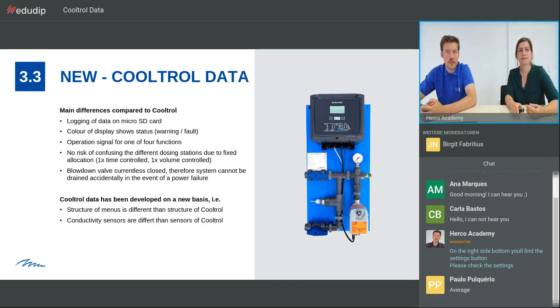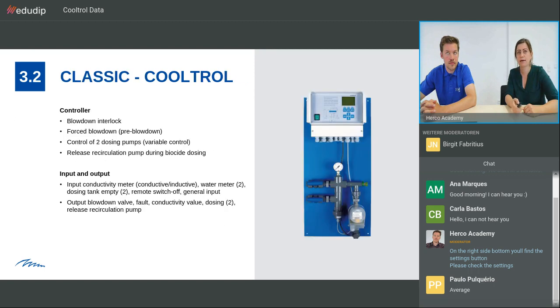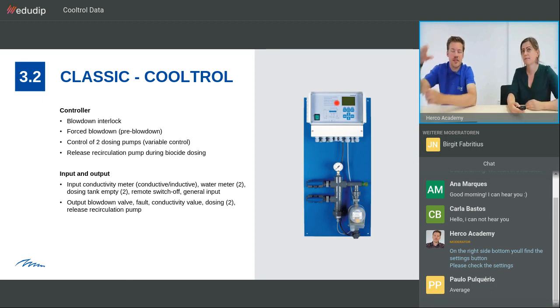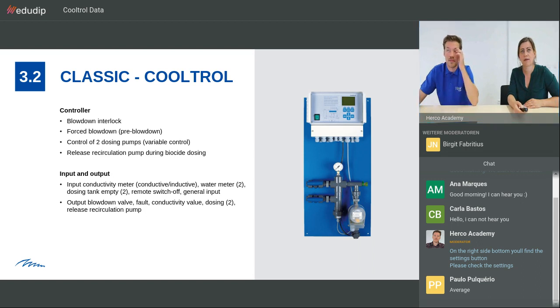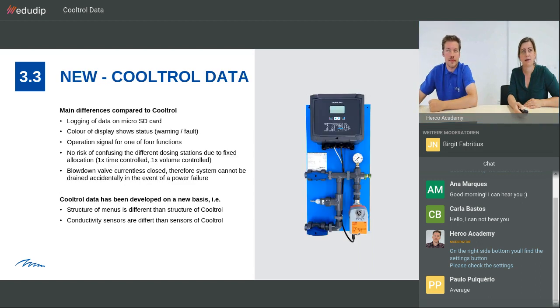Here we show the main differences condensed compared to the Cooltrol. Logging of data is new. So this we have in the Cooltrol data. We have the color of the display in the old Cooltrol. I'm just going to go back. You see you have LEDs there, so it's not that visible. Yeah, maybe you can show it. It's like status LEDs. It's hard to see on a small picture, but it's for operation, dosing 1, dosing 2, and everything. So it's basically just LEDs. Okay, and here you have really a color of the display. So warning will be orange and fault will be red. And since it's the whole display, it's really very good visibility.